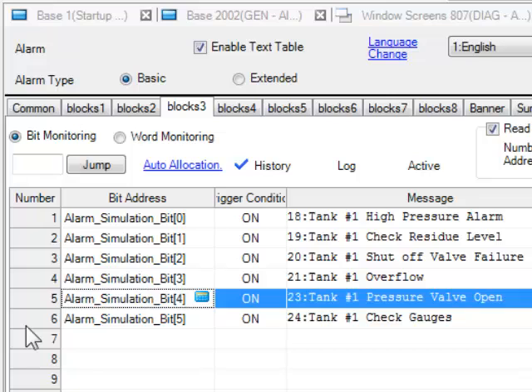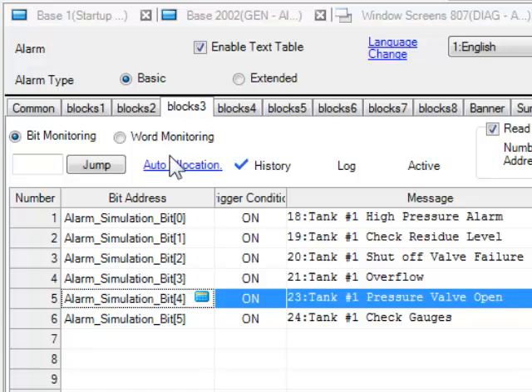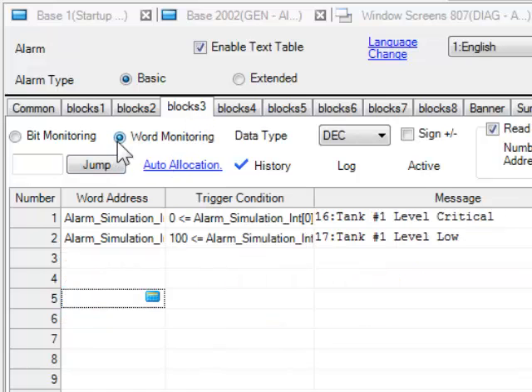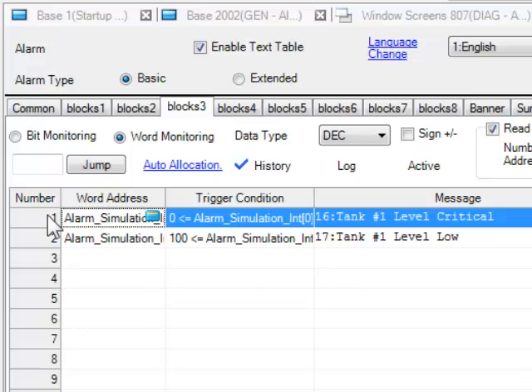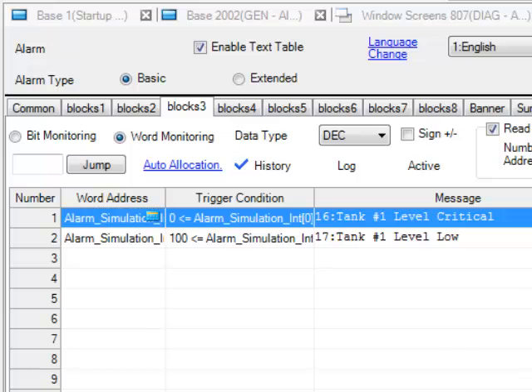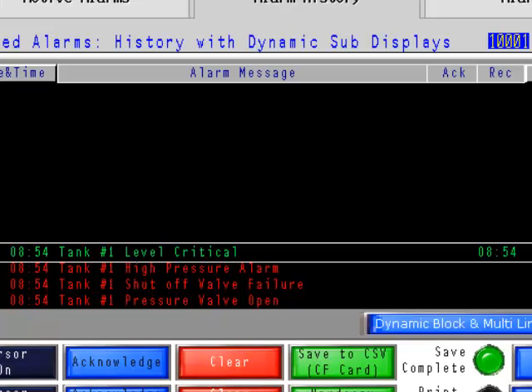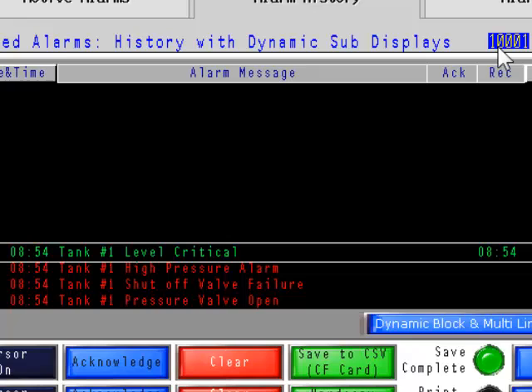What about the 10001? Well, these are all the bits associated with block 3 alarms. These are word alarms. And number 1 is tank 1 level critical. And there it is. So the cursor position is the number in the list. And then with an added 10,000 for word alarms versus regular alarms.